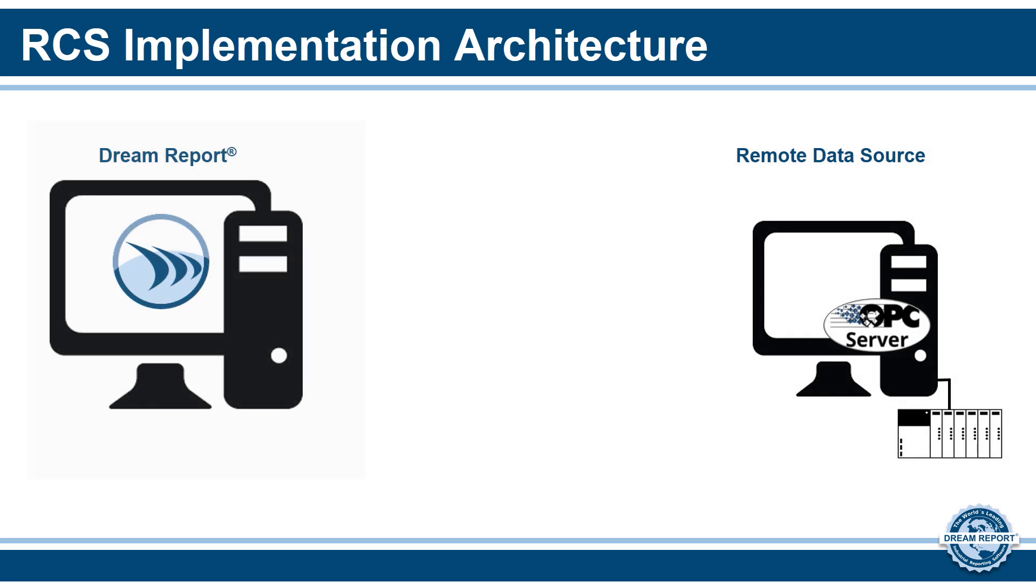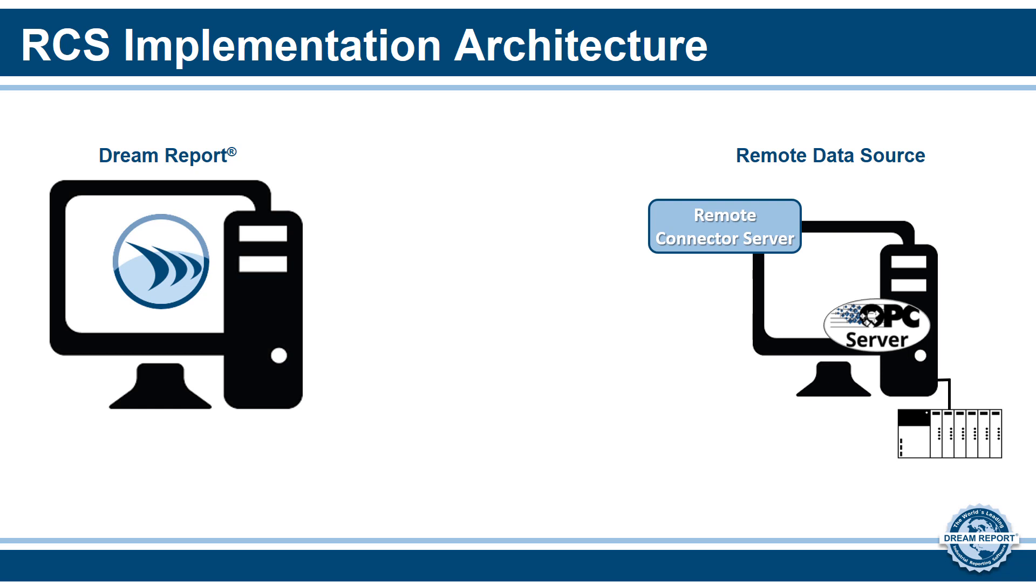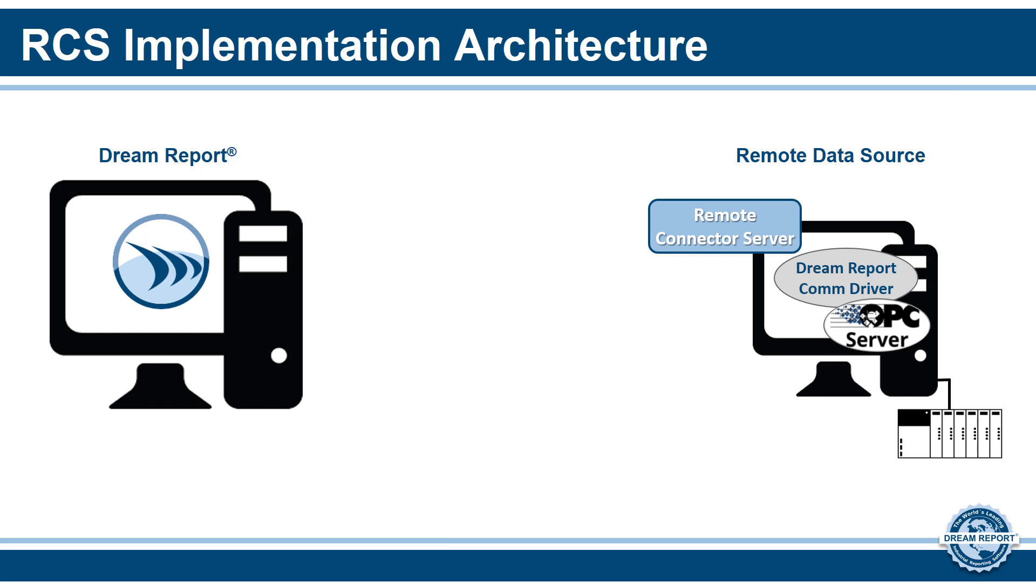The first thing we need to do is open the remote connector on the remote PC and configure its communication properties. That is, how the remote driver on the DreamReport PC will connect and communicate with it. We can also configure how the remote connector will start up and the log file detail level. Once that's done, we now need to configure one or more DreamReport communication drivers. Here, since we need to communicate with an OPC server, we have selected the DreamReport OPC DA Real-time Values driver and configured it to talk locally to the OPC server. We are now done with the remote PC and need to configure the DreamReport side.